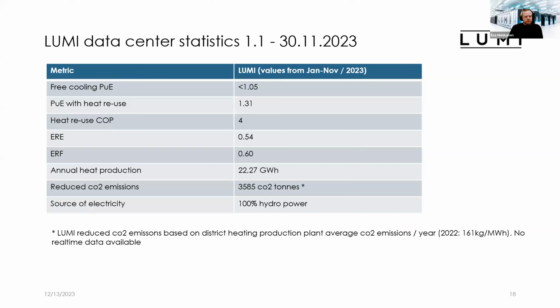So some values from the Lumi data center so far this year. These numbers were updated at the end of November. Our free cooling PUE is below 1.05 if we operate free cooling. PUE with the heat reuse is a little bit over 1.3, and this is something that we are aiming to get lower, below 1.3, in the future.